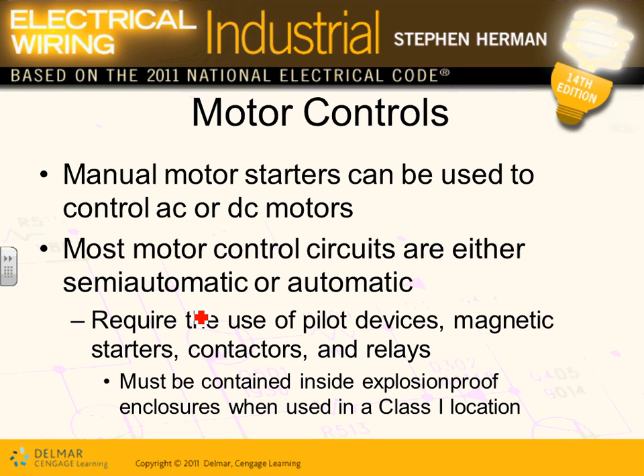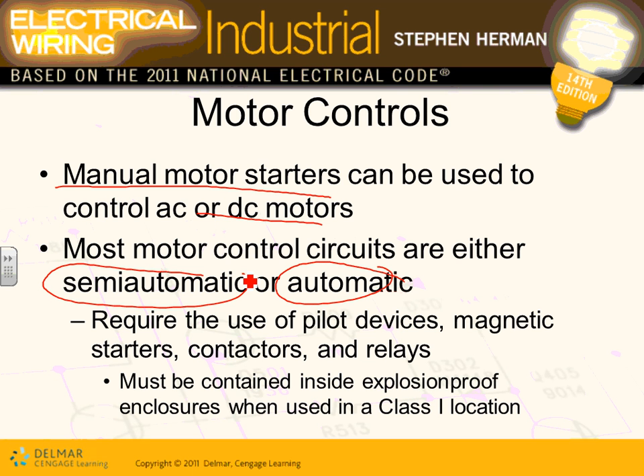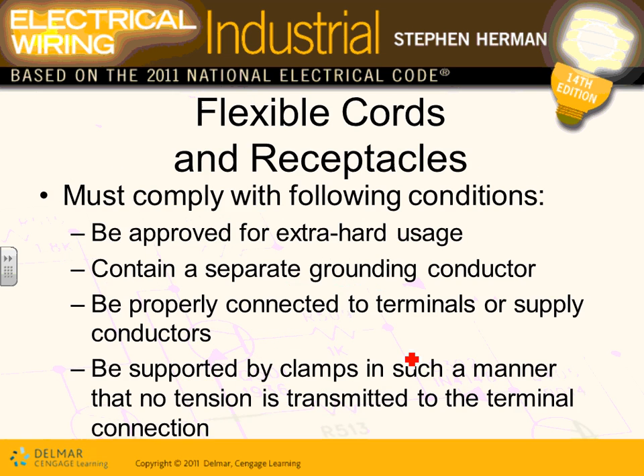Motor controllers. In this example, they're using manual starters or auto starters used to control your AC or DC motors. They can be auto, like I said, or semi-auto or manual. They require the use of pilot devices and magnetic starters and contactors. We talked about this one before. They must be contained. The most important thing hazard-wise is you always have to put them in explosion-proof enclosures. So your magnetic starter that costs you $100 now, all of a sudden becomes $1,000 because of the enclosure that you have to put it in. Very, very expensive piece of equipment.